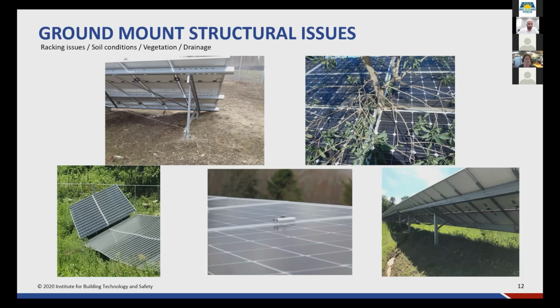Vegetation also needs to stay under the level of the array, or be mowed and taken care of. Otherwise you get situations like this, where a tree grew over about two years not only up between the panels, but was stressing the panel, stressing the rack, and shading the entire array.